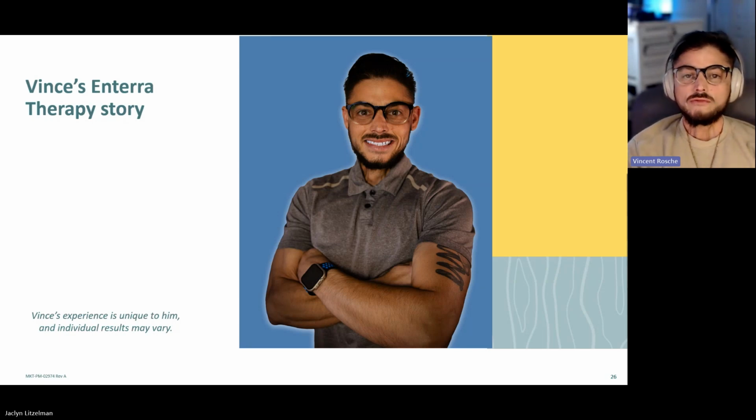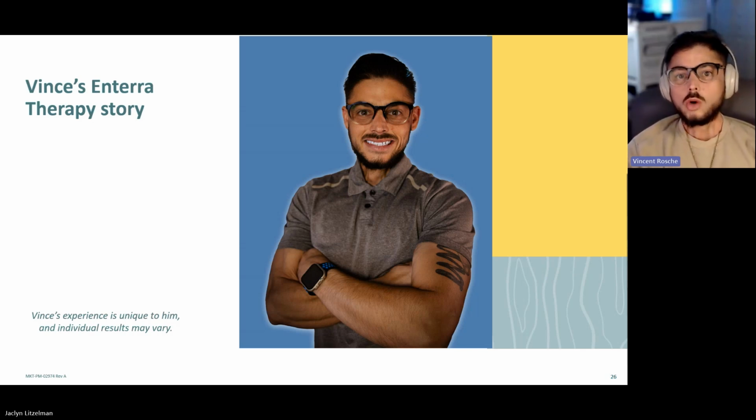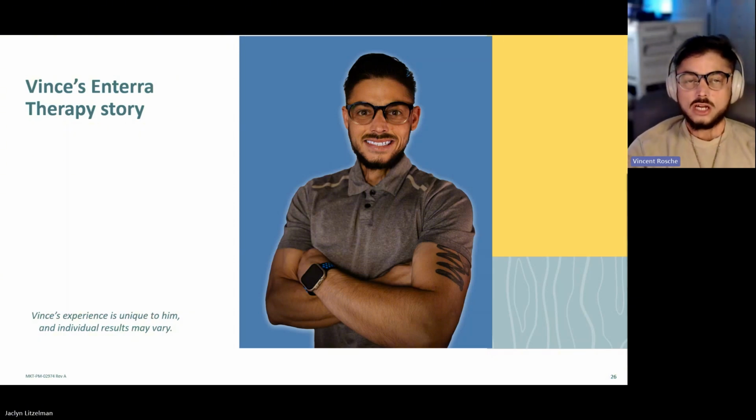And I would say over the first year, it really took a good amount of time to dial those settings in. But after about the first year, I really haven't had to adjust it because those first couple setting adjustments, we figured out what could work, what wouldn't work, the do's and don'ts. And now I've pretty much been on the same settings. I can't even remember the last time we changed a setting. It was really just checking to make sure the battery was still good and that everything was still working properly. But I haven't really changed a setting in, I can't remember, at least 5 years or so.